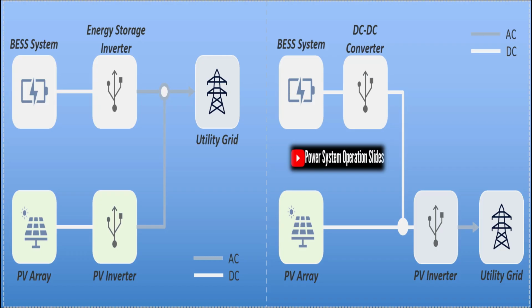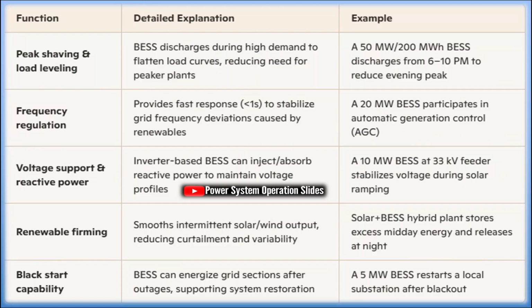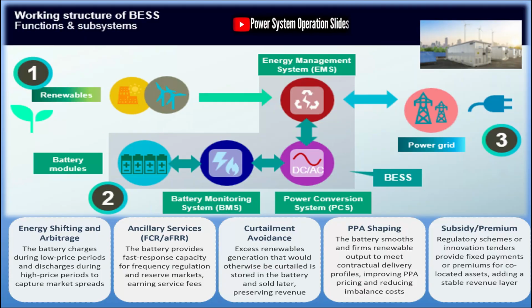Finally, islanding and black start support capabilities enable BESS to maintain operation of critical loads during system disturbances and assist in system restoration following blackouts, a capability that becomes increasingly valuable as the grid's resilience requirements become more stringent. The South Australia Hornsdale Power Reserve provides a compelling real-world demonstration of BESS capabilities in addressing these operational challenges. Commissioned in 2017, this 150 megawatts per 193.5 megawatt-hours facility was initially conceived as a response to the South Australian energy crisis of 2016, during which multiple system blackouts highlighted the vulnerability of a grid with high renewable penetration.